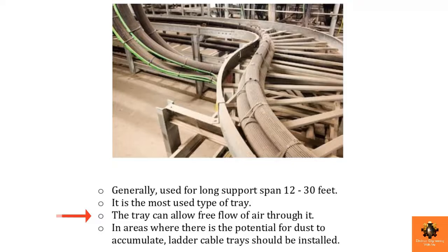So for that reason, many of the consultants use this ladder type cable tray. In 75% of projects, consultants go with the ladder type cable tray. And the ladder type cable tray is also recommended for areas where we have dust problems. So this is the ladder type cable tray.